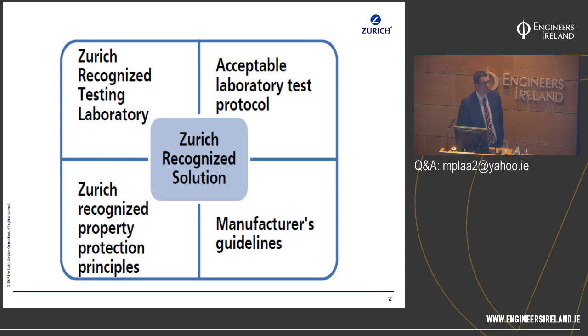Currently, in Ireland, we would rely on the British standard for domestic sprinkler systems. So therefore, there is a coded design, installation, delivery system for domestic sprinklers. What about the same situation for water mist, from your own experience relative to efficacy? Yeah, so we're seeing in the market back home, systems in the domestic market being installed to BS 8458, which would be looking at an alternative to residential sprinklers, and using that instead of residential sprinklers.